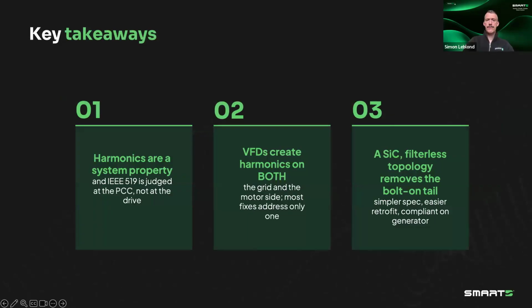Okay, and now in terms of conclusion, maybe just three things to take away here. When we talk about harmonics and compliance to IEEE 519, you really need to think about it at the system level, not at the device level. They do exist on both the motor side and the line side. So talking about harmonics only for the grid is actually cutting half of the equation out of the problem.